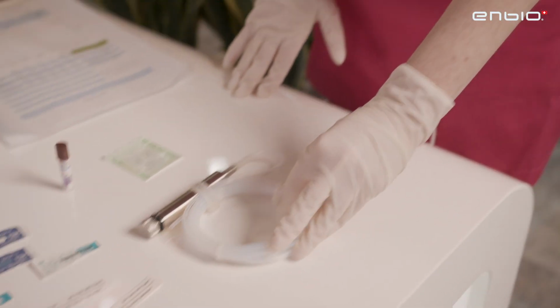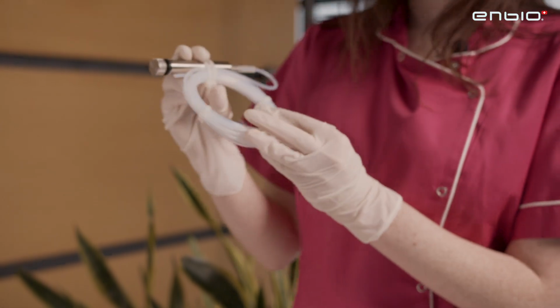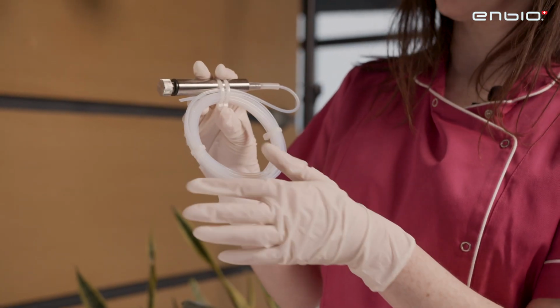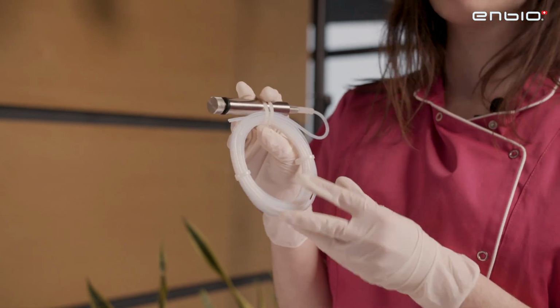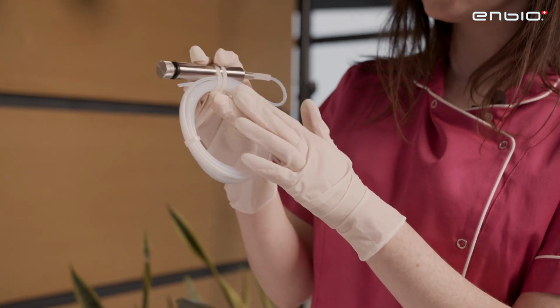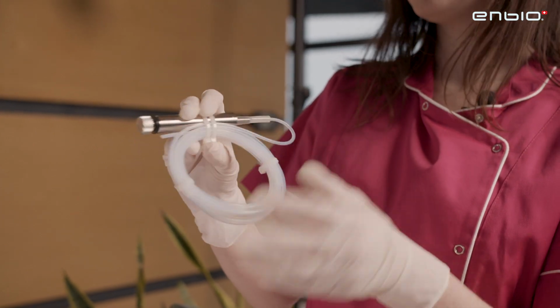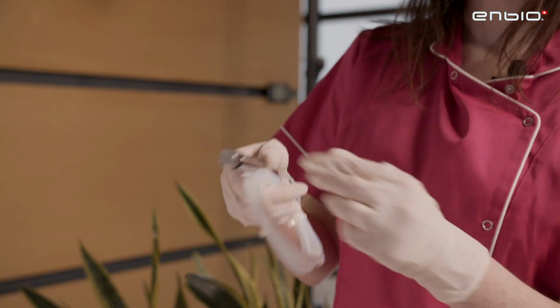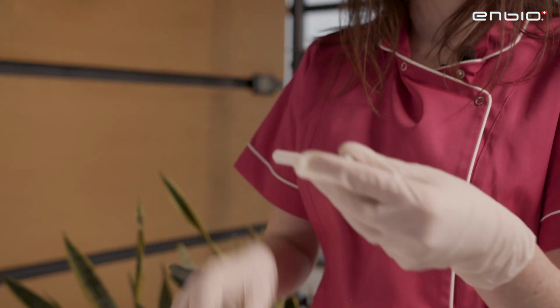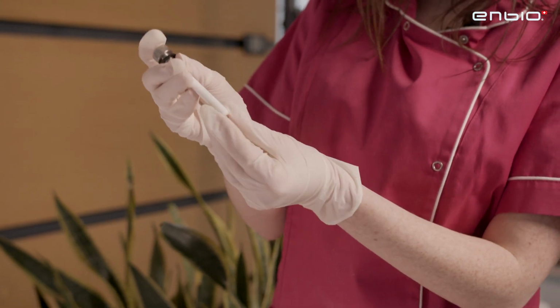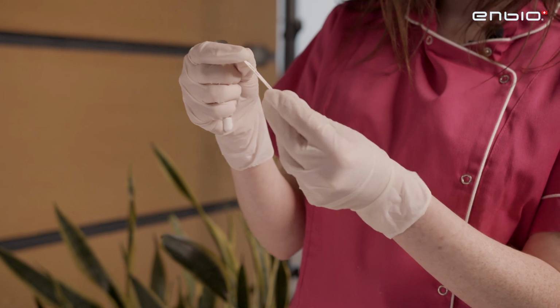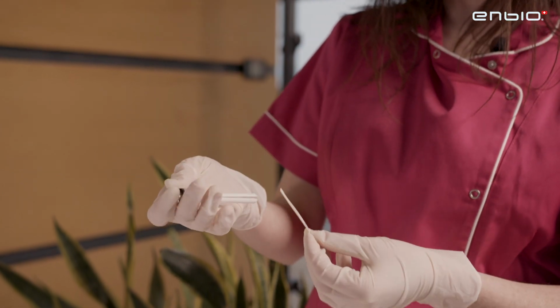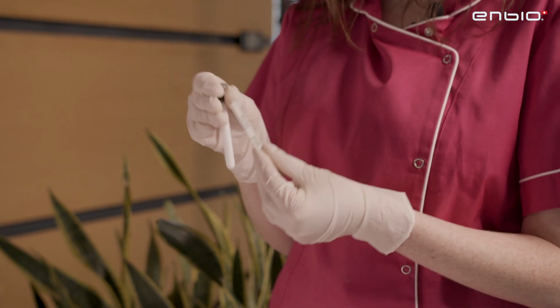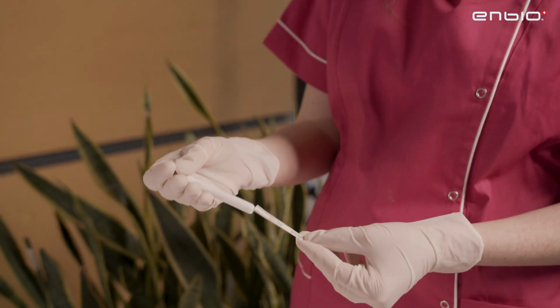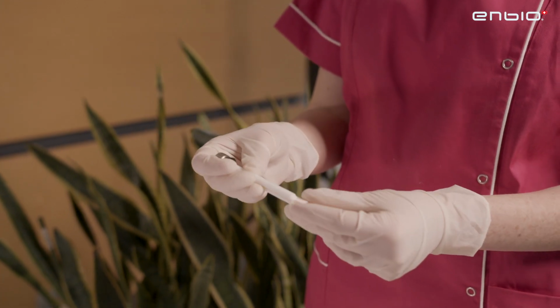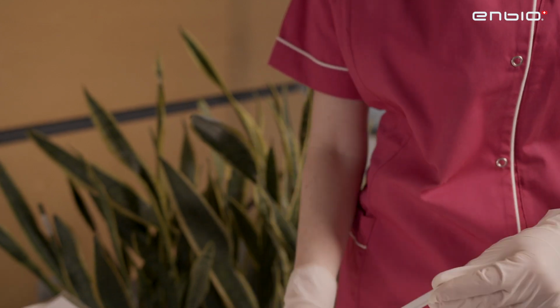Let's move forward to the helix test. This is how the helix test looks like. As we can see, it has a quite long tube with a diameter of only 2 millimeters, and the steam has to penetrate inside the whole tube and get to the end of it, where we have a chemical indicator inside, which will confirm if the test was passed or not. So here is the chemical indicator. And this test is supposed to check if we indeed can sterilize all kinds of tools inside the autoclave. And in order to perform it, we need to select the special test from the menu of the autoclave.